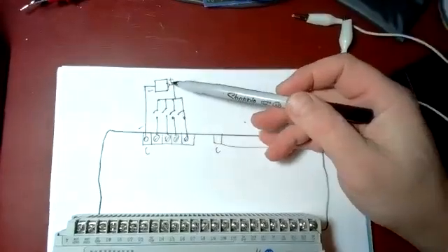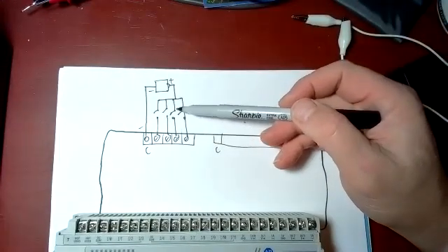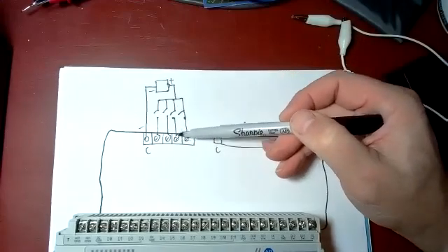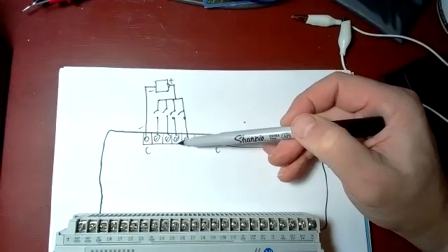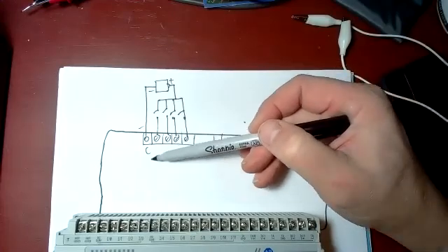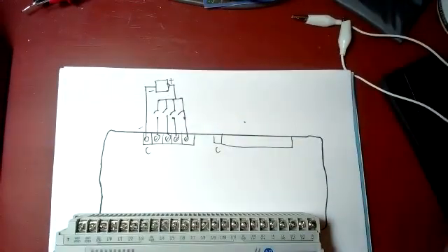I would want to provide the back side of that switch with plus 24 volts. When I close that switch, energy can flow through the switch down to the input. Now the input sees plus 24 at this terminal, and then energy can flow inside the PLC out to the minus and turn on that input for the PLC.